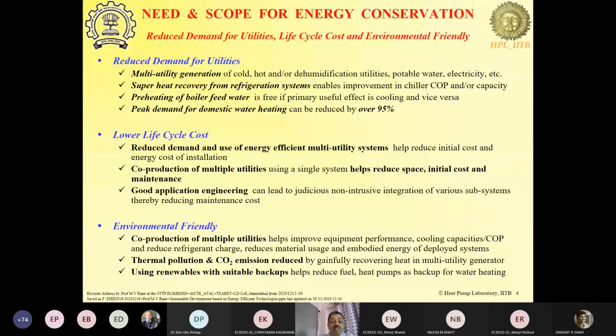Of course, we'll look at some of the challenges in meeting multiple demands using a single system as we go along. So now we'll also look at low life cycle cost. How can life cycle cost be reduced? First, you reduce the demand and usage by using efficient multi-utility systems to produce the utilities that are required. That is going to reduce the size of the equipment, so your initial cost can be reduced. Instead of multiple systems catering to multiple utilities being generated independently, a single system generating two utilities can be cheaper at times.